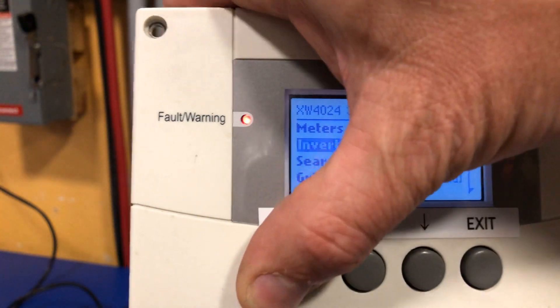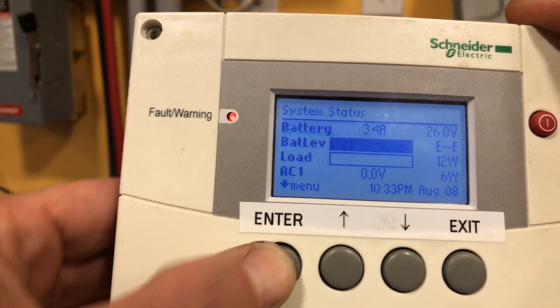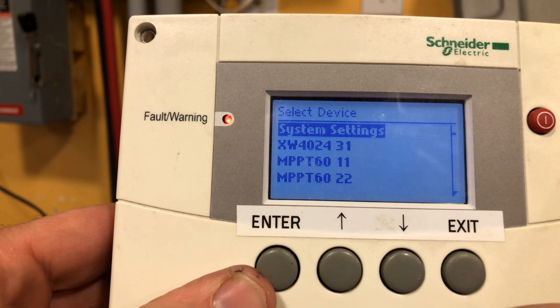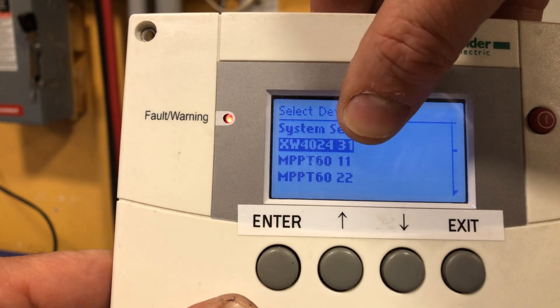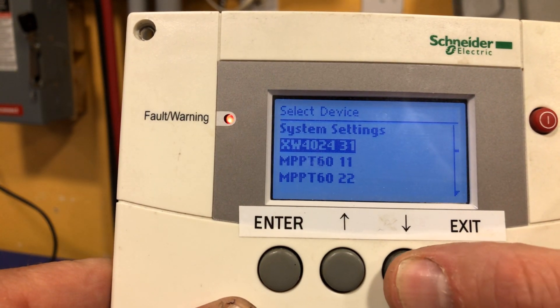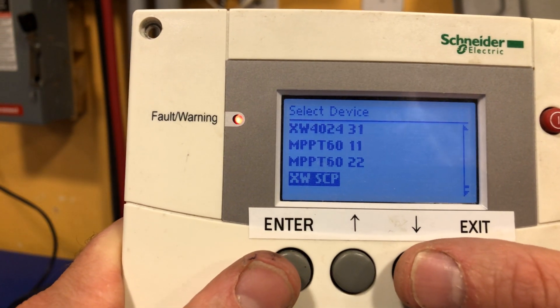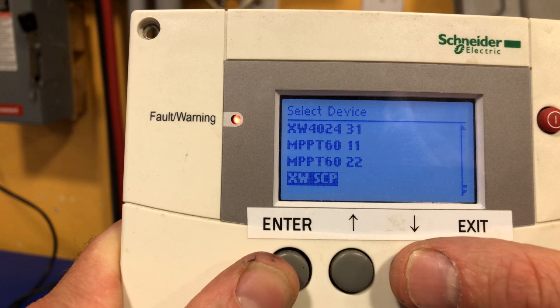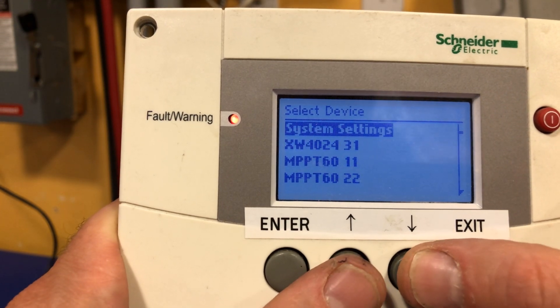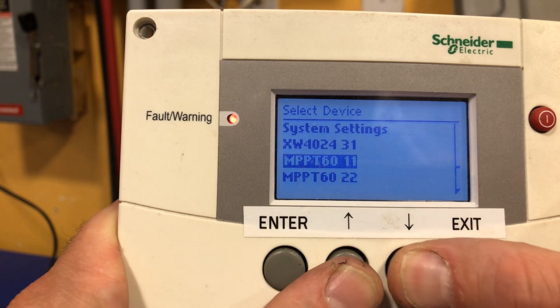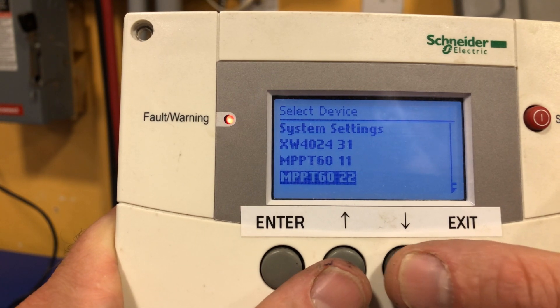Let's go ahead and turn the inverter on starting from the very top. What we're trying to do is confirm that each of the devices has their own unique identification number — the last two digits right here. If they don't have their own unique identifier, there's a conflict on the network. The challenge is the system control panel defaults to device 00, and so do all other new devices when they come onto the Xanbus network. So the 4024, MPPT60, and second MPPT60 would all come with a unique ID of 00.